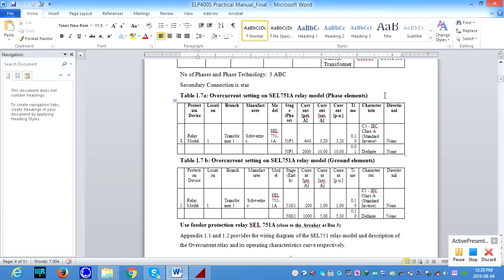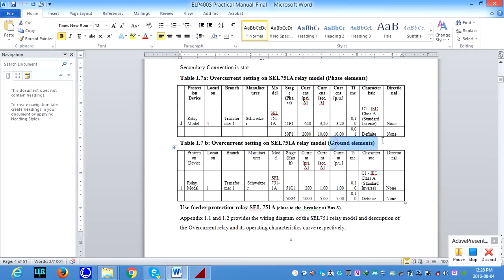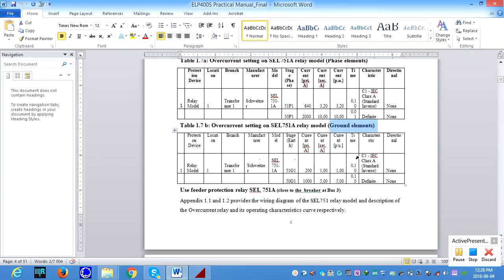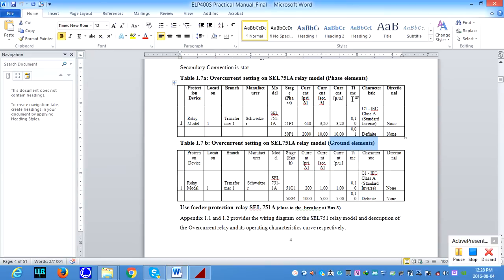I want to give an overview about the phase element and the ground element. Keep it in mind, the phase element is the one if there is a three-phase symmetrical fault on any location of the network that can be detected with the phase elements. I think this one is for three-phase faults or line-to-line faults. Okay, but even that is a phase fault. But if you have a line-to-ground fault, either a single line-to-ground fault or double line-to-ground fault, so we need to make sure the settings for the ground elements for the ground faults. Okay. Let me move on.